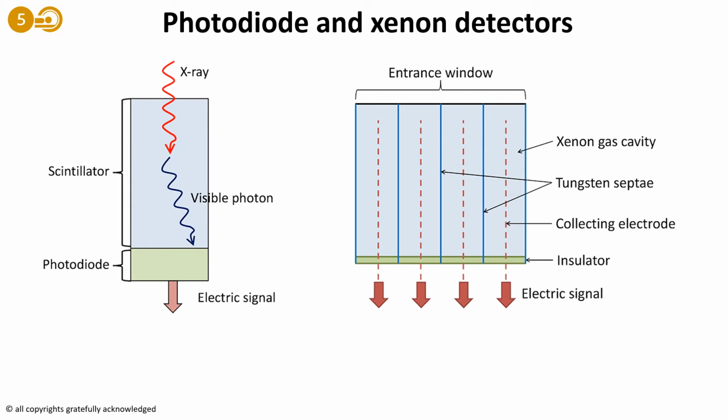And that has consequences in terms of crosstalk between the detectors, and to try to mitigate that, you end up with a shorter piece of xenon gas than you might otherwise have, and that would cause lower dose efficiency in the detector. And basically it's turned out now that using a scintillator is currently preferred to using a gas.